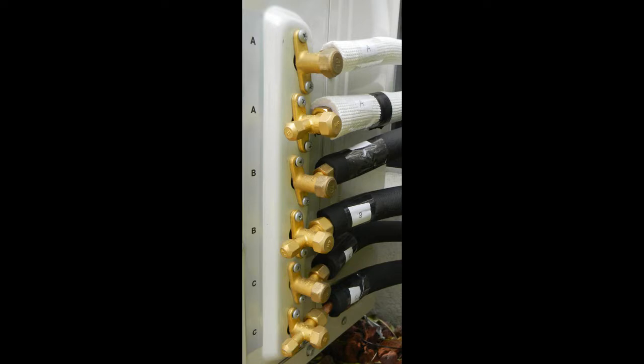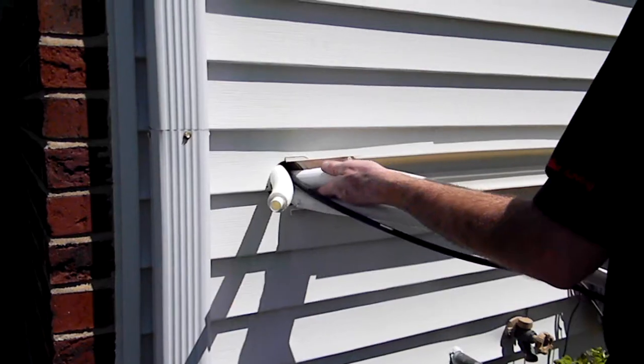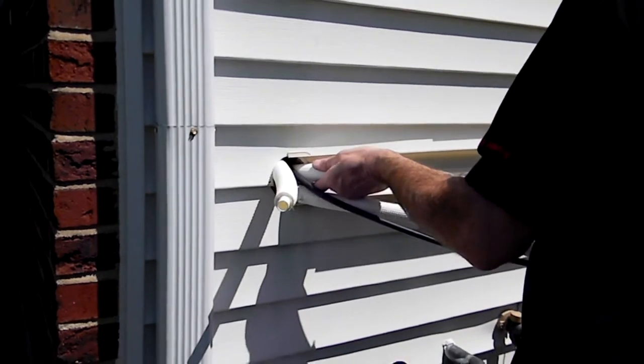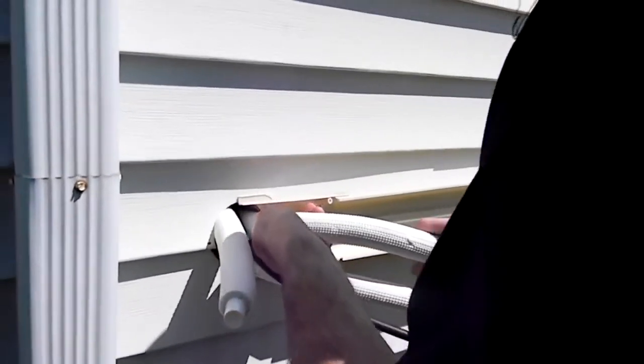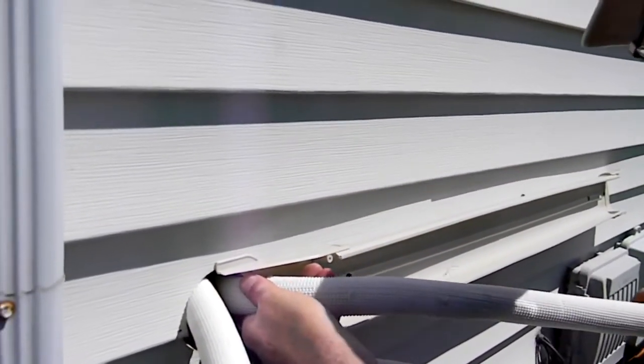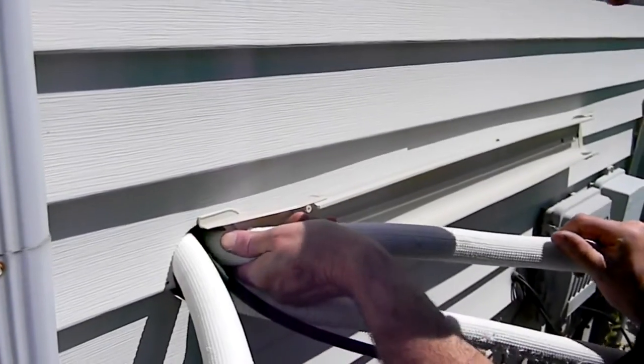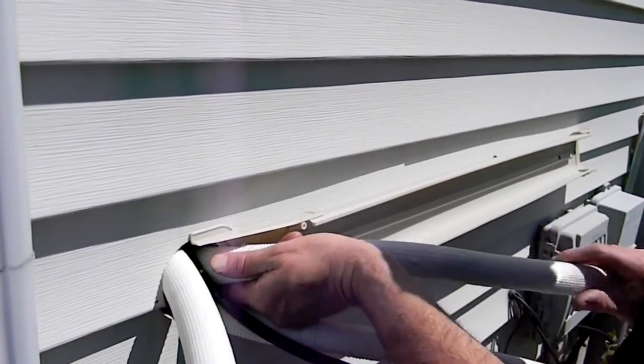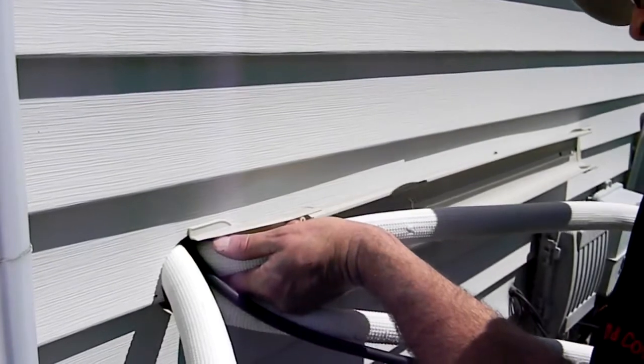YMGI strongly recommends marking all piping and wiring to their designated zone to eliminate the possibility of cross-wiring or cross-piping in the zones. These two conditions can cause damage to your unit and will disqualify it for the factory warranty. Carefully shape the tubing and direct it to the outdoor unit. On this line, we did not wrap the pipe because of the diameter of the suction line. This was done to prevent any kinking.